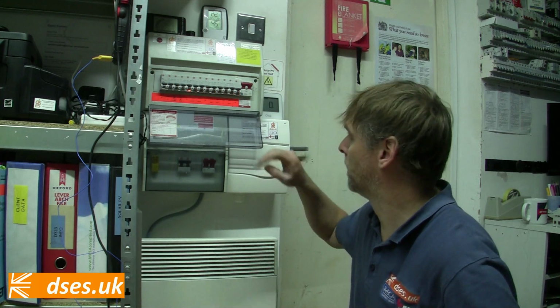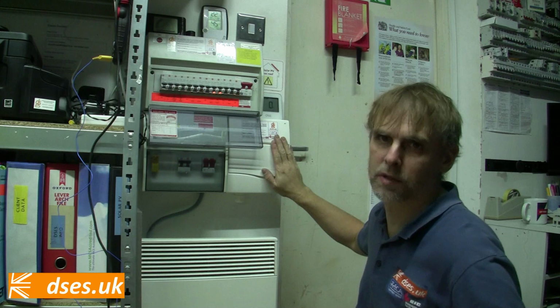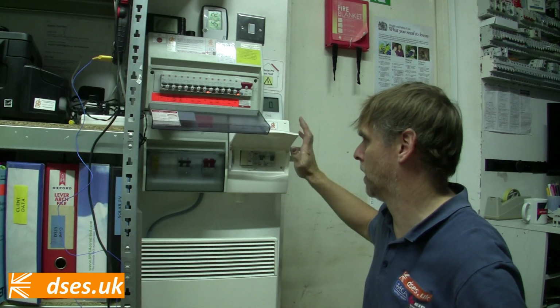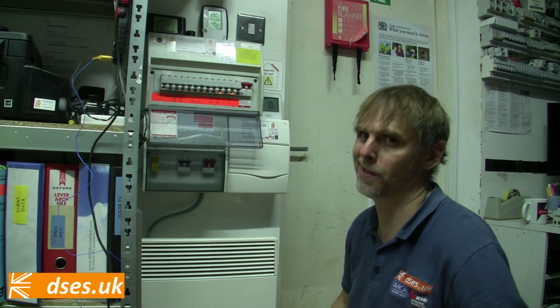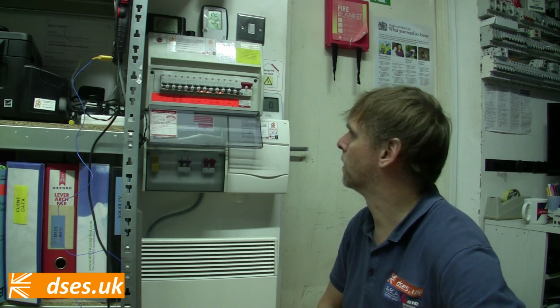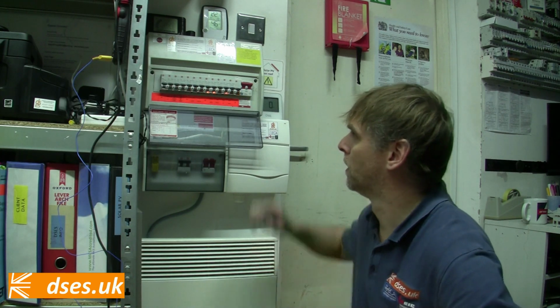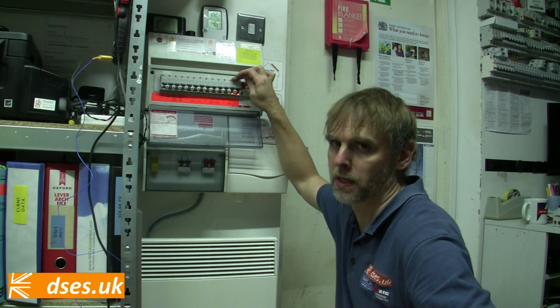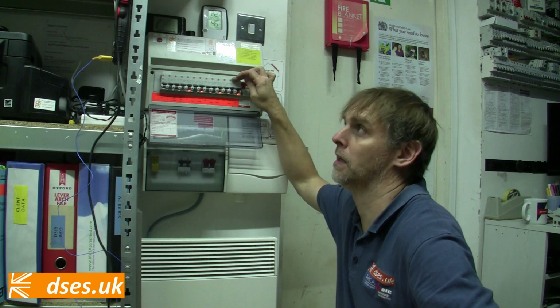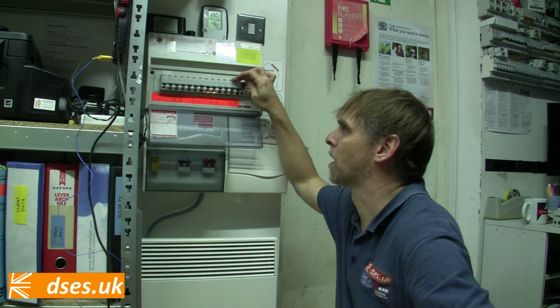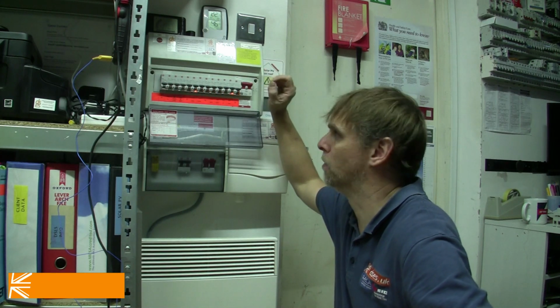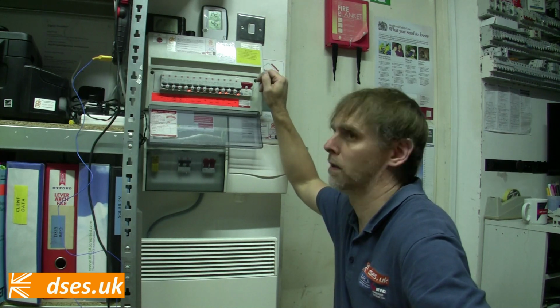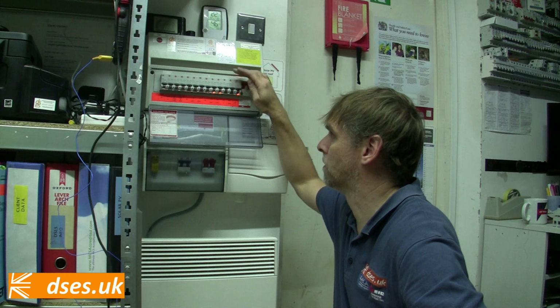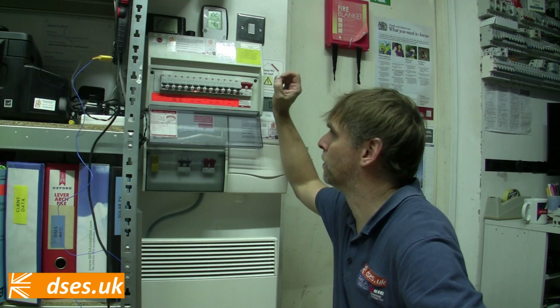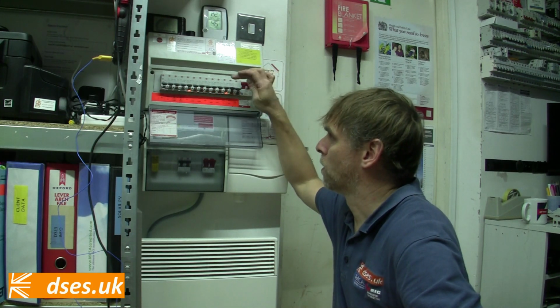A quick run through of what we've got here. I've got a 40 amp AFDD for DB3, which is my shower and car charger. If anything's going to fail on an arc fault, that's a high contender, because we've seen shower isolators, I'm sure, in the past that have burnt out, so that's one where it may happen in the future. Similarly, the one neighbouring it, which is the water heater, the immersion heater, I've had problems with that before, with the timer controls on that. And in my test and inspect last week, I did find a loose neutral on that, but it's all nice and tight now. For some reason, it never seems to stay that way. So these two here are the ones that my money is on tripping in the future should something go wrong. Solar PV is next, 16 amp breaker.